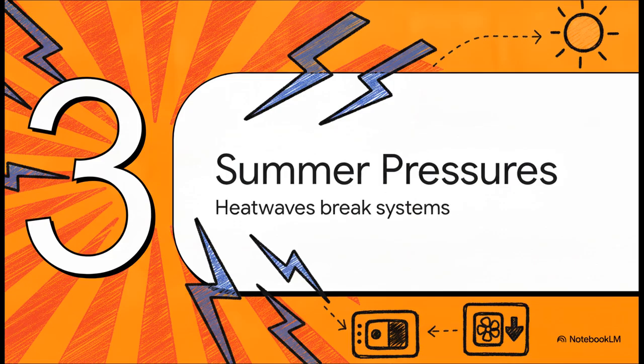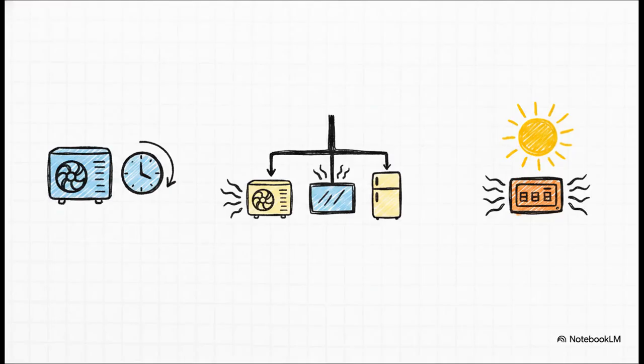That brings us to Section 3, Summer's invisible pressures. Why heat waves break the system. Summer just adds two very specific environmental and mechanical pressures that push these protective mechanisms to their absolute limits. First, your cooling equipment is running much longer. Second, it might be sharing a branch circuit with other heavy loads. But crucially, consider this third point. The ambient air surrounding the breaker box itself is already baking hot. And honestly, that's the secret ingredient for a sudden power drop.